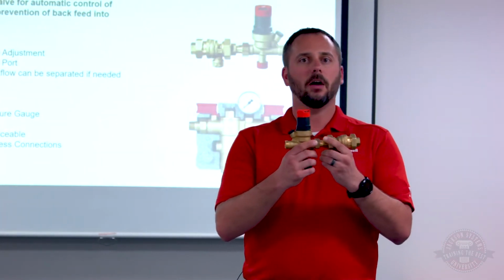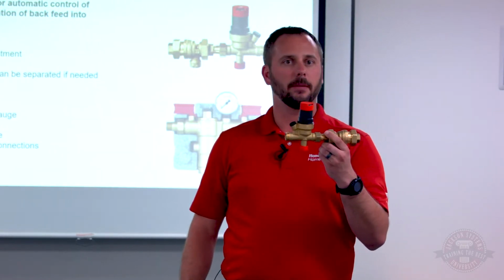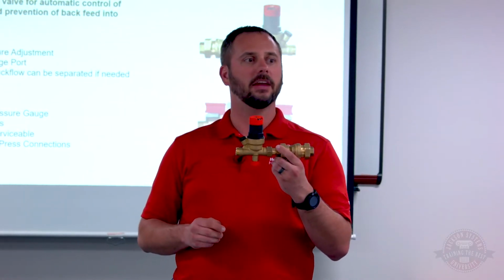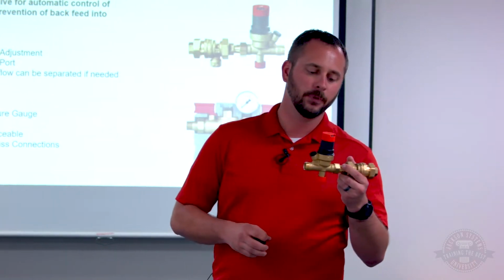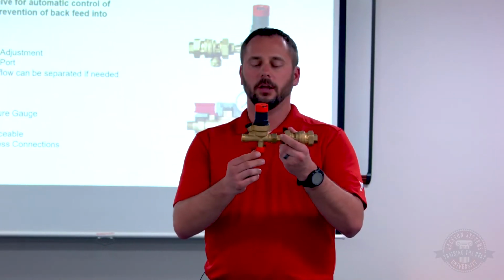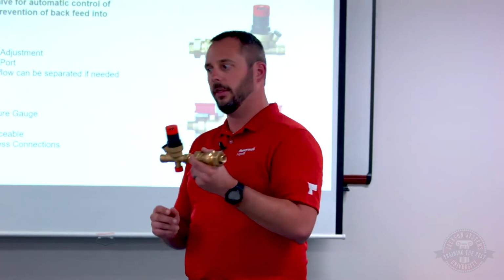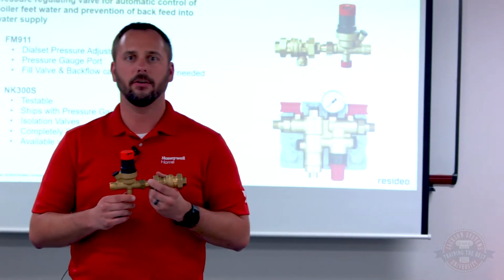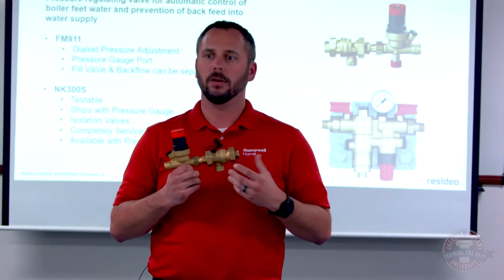So you hook this valve up, and you're basically setting your pressure. Your incoming pressure could be at 60, 80, whatever it is. You're going to reduce it down to 15 psi. And I'm going to talk about a little bit of the sizing and what that means and why we select those pressures here in a little bit. But the other thing I want to show you on this is at the very bottom, we have a shutoff valve.